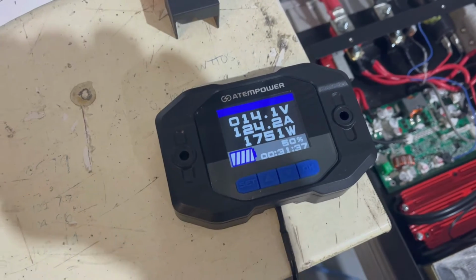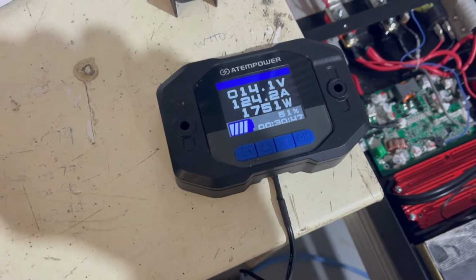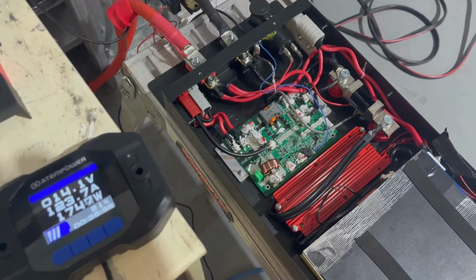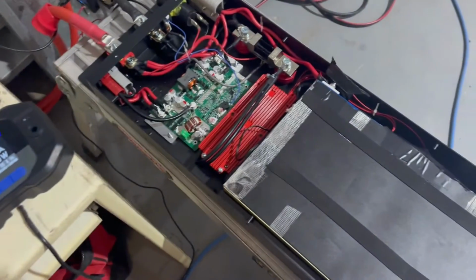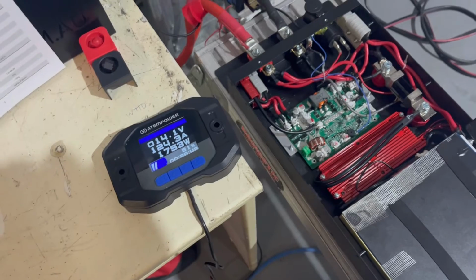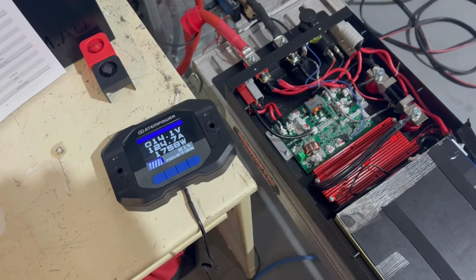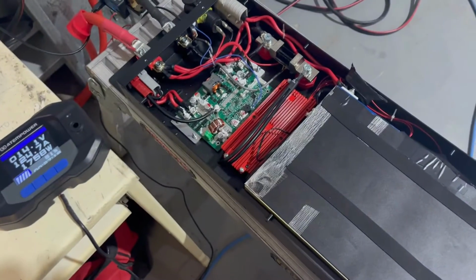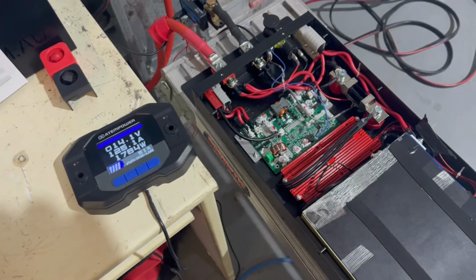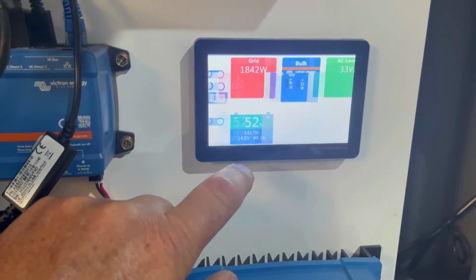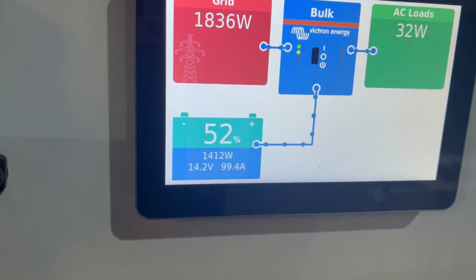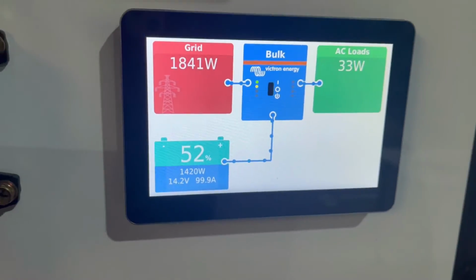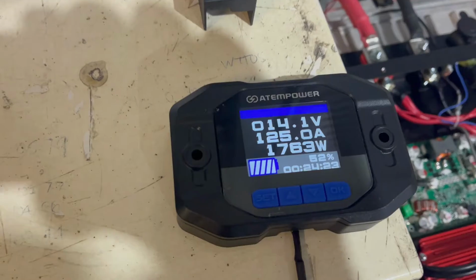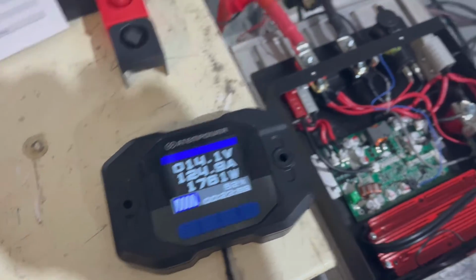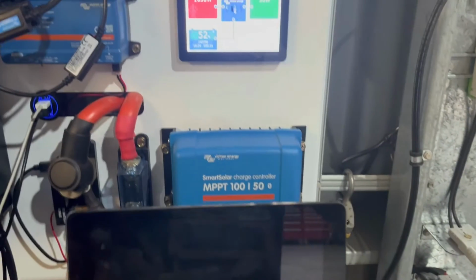I mean, it's not 123 amps, so you'd expect that to hold. Normally they rate them about 10% over, so you might put it up a bit more, like 110, 115, and see whether it cuts out. There you go - it's saying it's got 99 amps going into it. Here we're showing 125 amps. I've also got it set at 14.6 volts charge, which was what was in the spec of the thing.